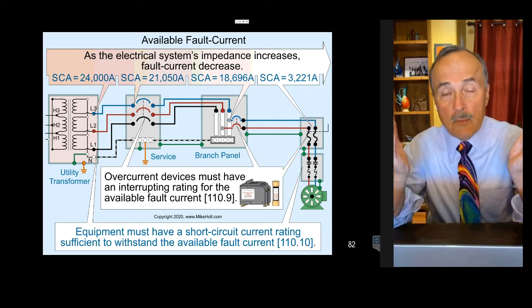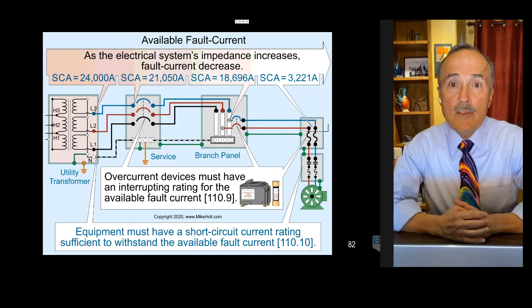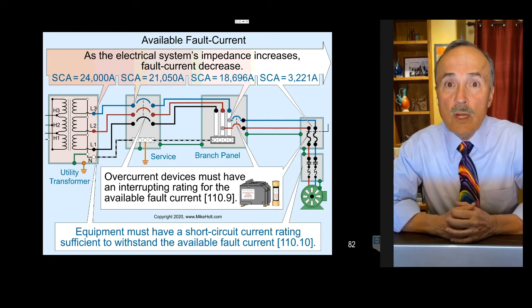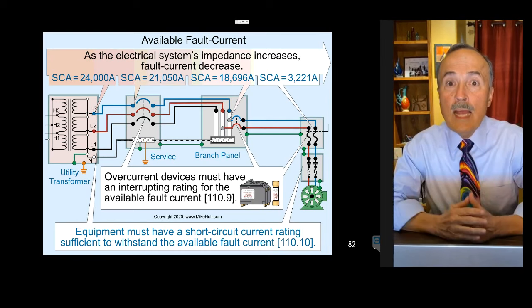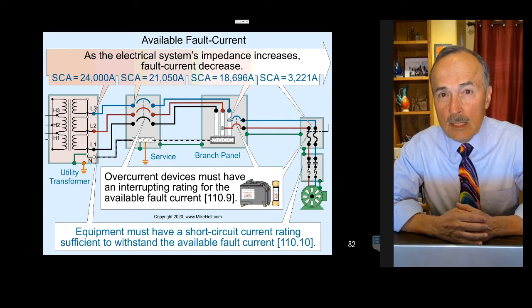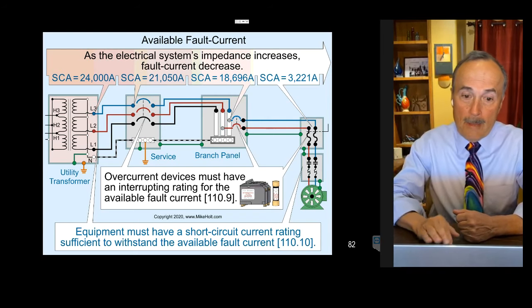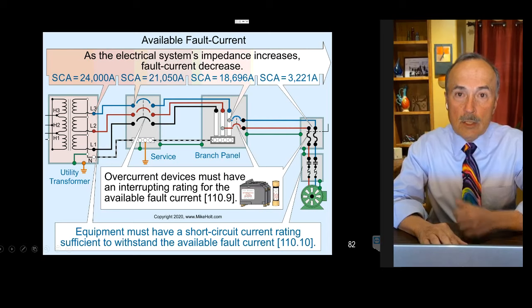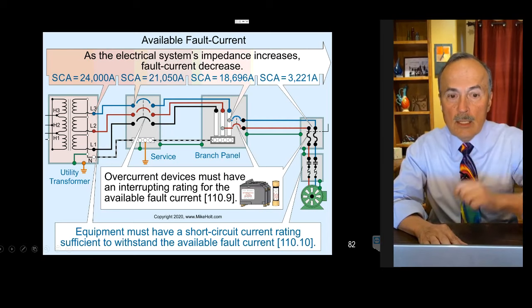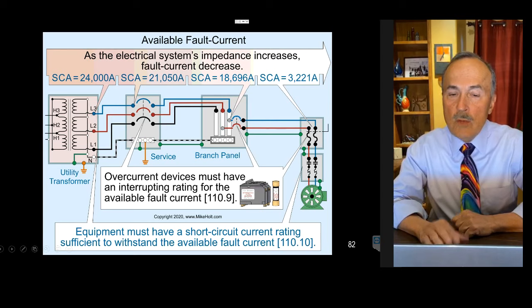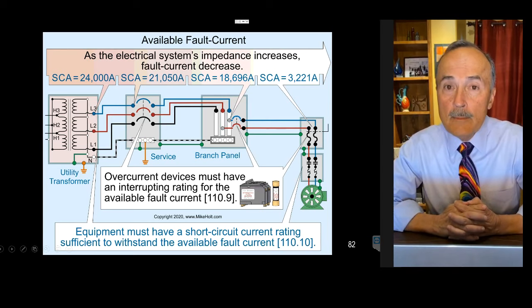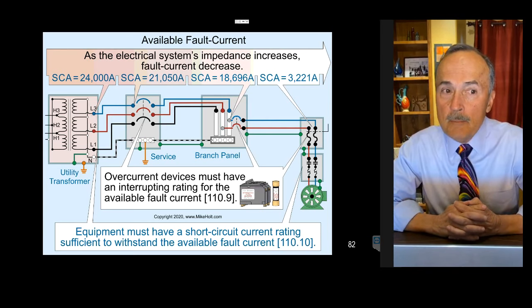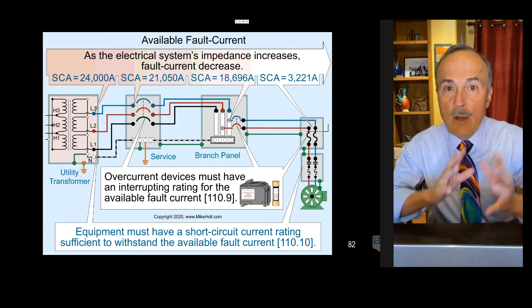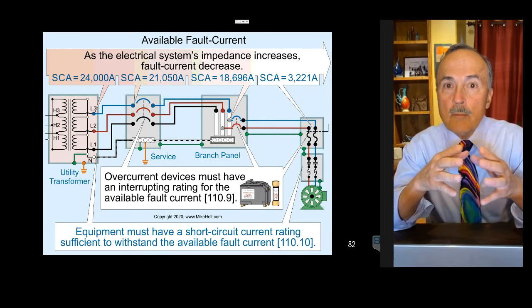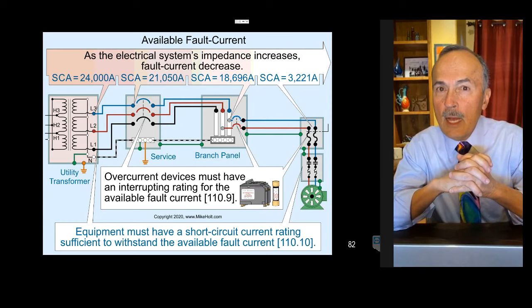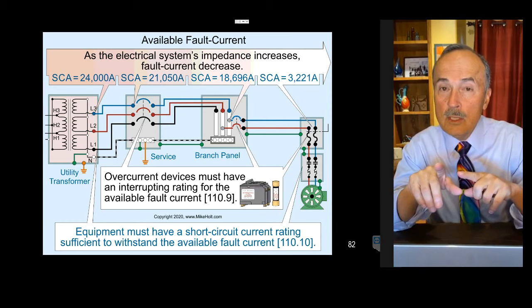It has a certain length, okay? And it's aluminum, or it's copper, or it's in a metal raceway, or it's in a PVC raceway. So you have all these different factors. And then you'd have to have software to say, hey, listen, I'm running 500,000 and I'm going to be running at 80 feet. And the available fault starts at 24,000. What's the fault at the line side terminals of that service disconnect means? Because we need to know that information. So you do a calculation. There's a spreadsheet. There's a calculator that does that. And guess what? They say it's 21,050.